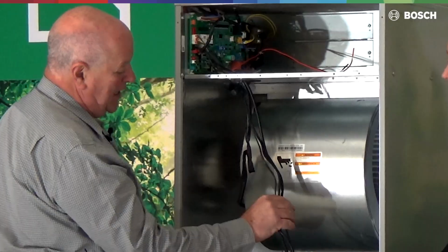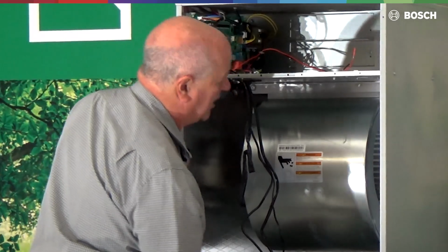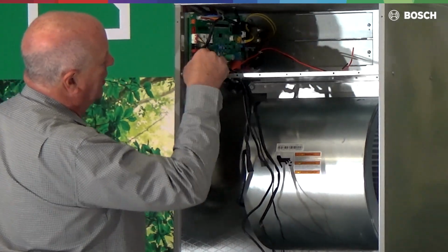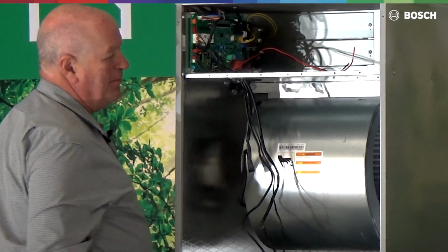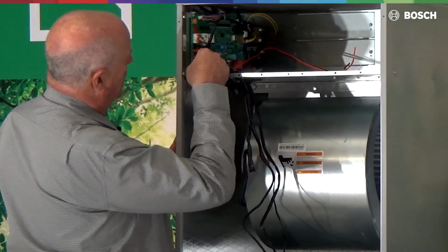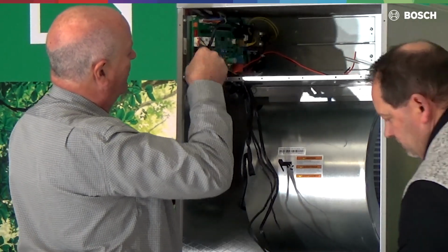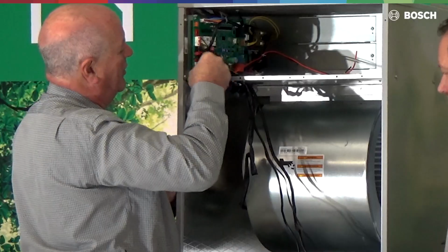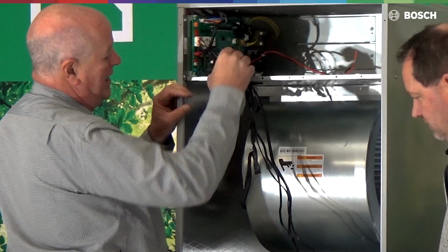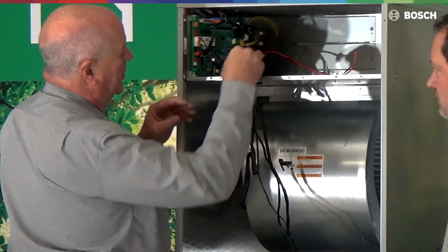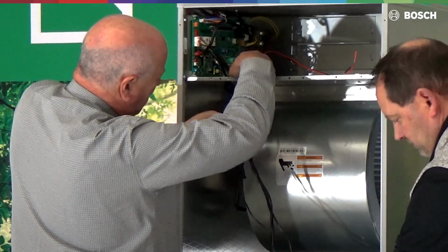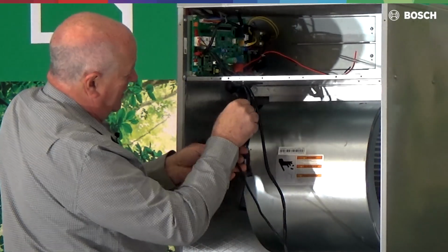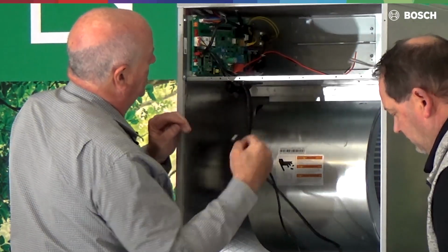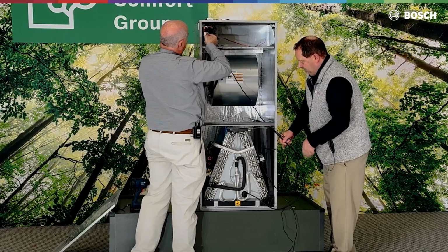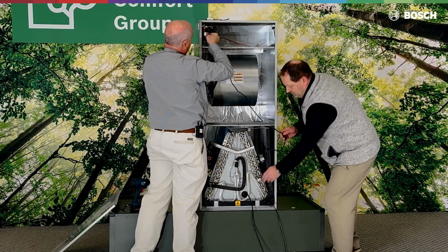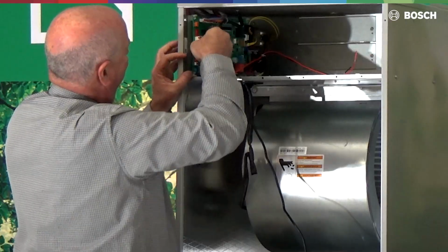So guys, we have our T1, T2 sensor and A2L sensor. They're located up on the board and they're marked as such, so you really can't mix that up when you go to take them apart. Some of these have clips, some don't. The T1, T2 does not have a clip. Those came out relatively easy. We'll pull them down through. You have to watch the grommet up here so we don't pull the end off. There's one for you, there's 2. And now we're going to go for the A2L sensor. We'll wiggle it back and forth a little bit. There she comes.